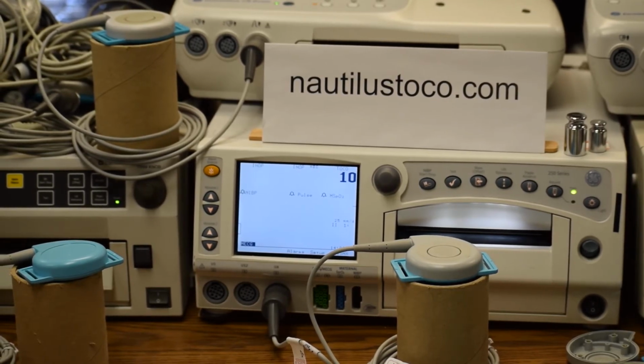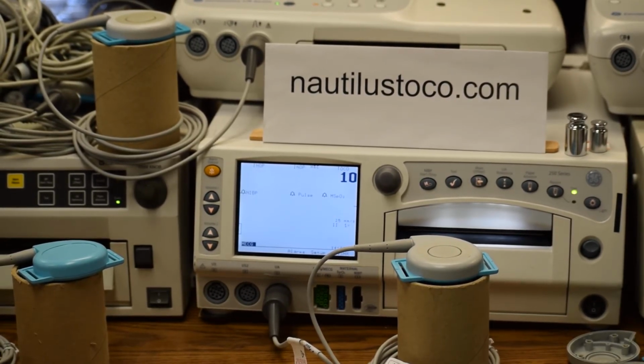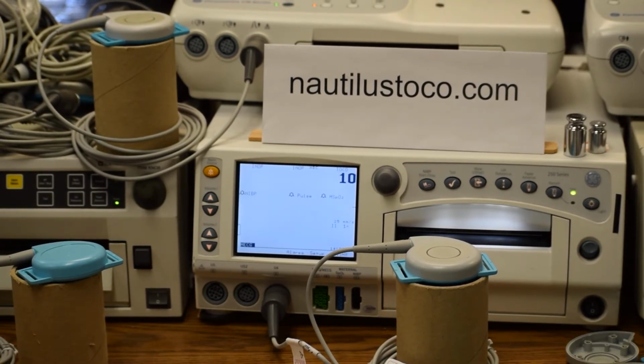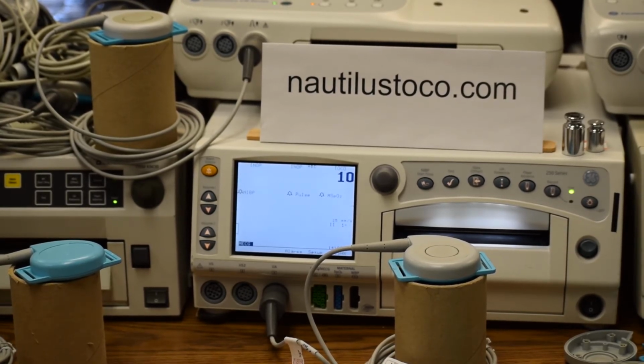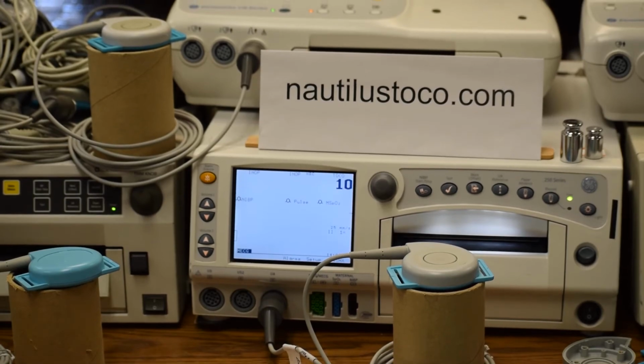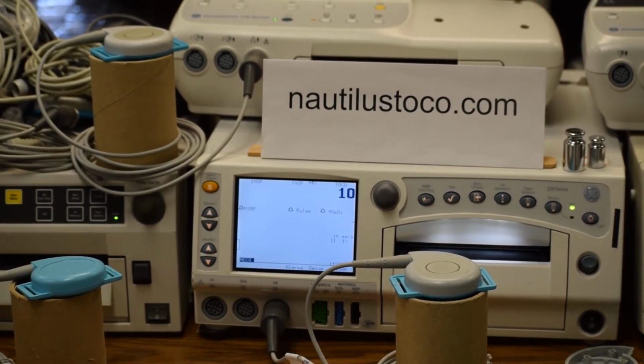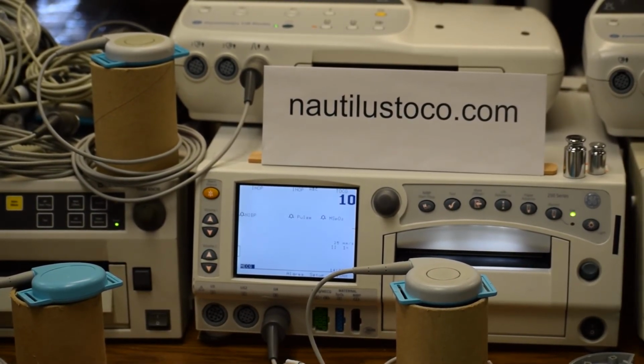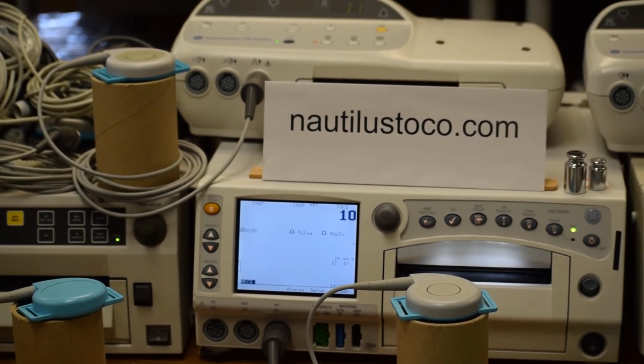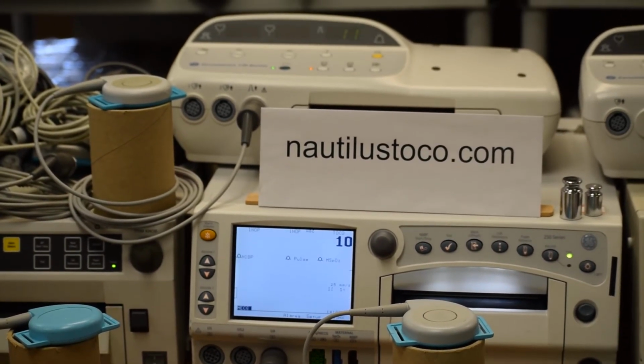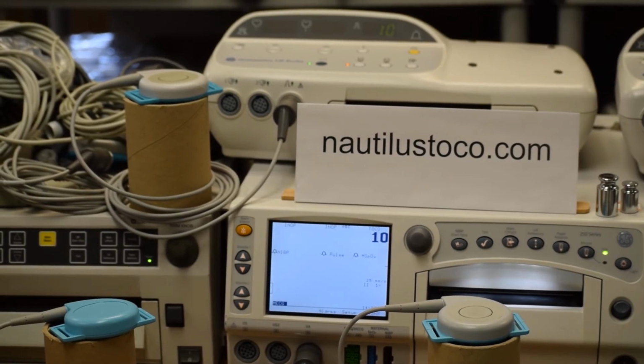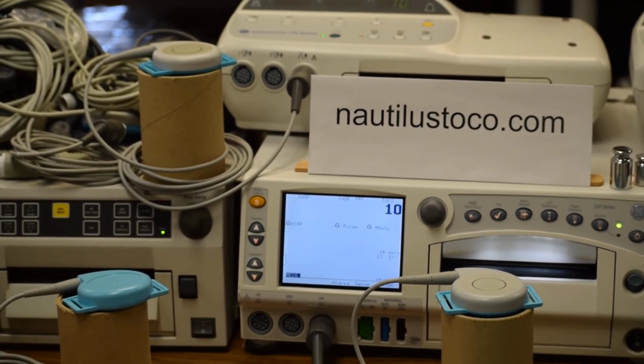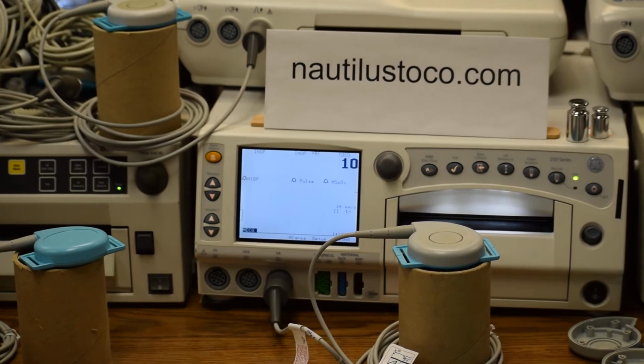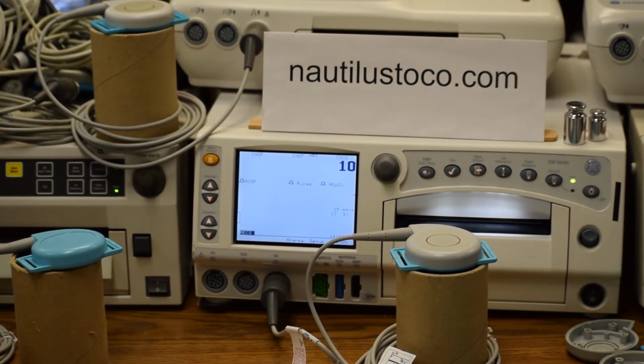Always coil the cable circularly more than 6 inches in diameter, or stretch it out straight completely to increase the functional lifespan of the transducer. That means never bend the cable sharply. It will certainly increase the lifespan. Don't use any tapes, glues or that sort, and use a twist tie when you coil the cable.